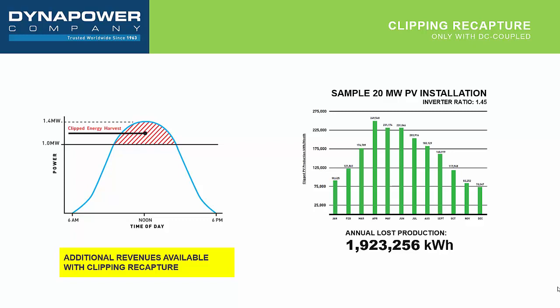If you have an inverter loading ratio of 1.45, you're actually going to see clipping throughout the year. And the numbers become substantial. At the end of the year, you may have upwards of 2 million kilowatt hours of lost production, which could otherwise be captured if you have a DC coupled storage system there. Now, we'll be quick to note that from a developer's perspective, it's typically hard to justify the addition of storage simply to capture the clipped energy in this sort of configuration. So think of the clipped energy as an important value add, a very important value add, but it has to be part of a larger value stack to ultimately make a storage plus solar system pencil.